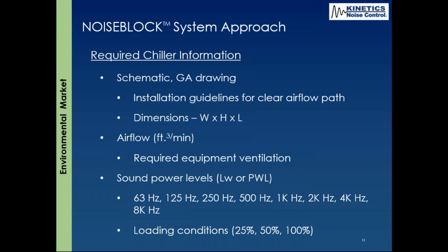We need the airflow rate. We want to know how many prop fans there are, how much total airflow in cubic feet per minute there is. And then we also want the sound power levels. You'll see a chiller manufacturer will have a chiller data sheet with sound power levels for each of the 8 octave bands, 1-to-1 octave bands, 63 hertz, 125, 250, all the way up to 8,000 hertz. That's perfect. That's what we need. Loading conditions: we'll ask the acoustical consultant to say, okay, if you took readings in the field at maybe various loading conditions, 25, 50, or 100% loading of the unit, let's look at how those compare to the actual published data from the manufacturer.